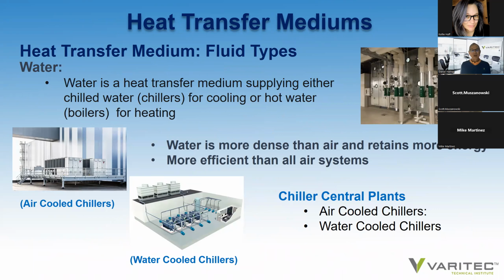So let's look at water as a heat transfer medium. Water is very efficient in moving energy because it is so much more dense. And water is used to be distributed through conventional all-air systems to the cooling coil of an air handler. If we bring chilled water to an air handler at about 44 degrees, the goal is to bring the sample of building air to 55 degrees, or dew point, to not only remove the thermal energy of that sample of air from a building, but also to remove the latent energy, or the water vapor, from the sample of air. Also, we can use hot water coils in air handlers to add heat energy when we're in heating mode. Water, again, is more dense than air, retains more energy, and is more efficient than all-air systems.